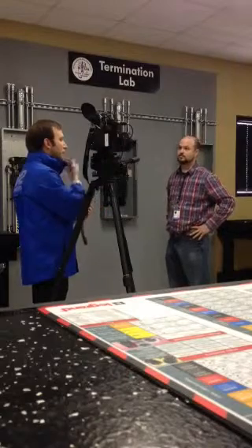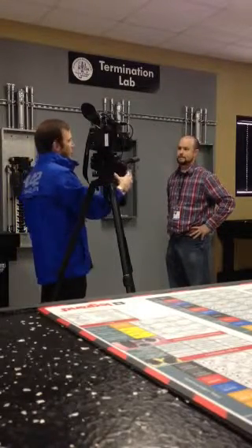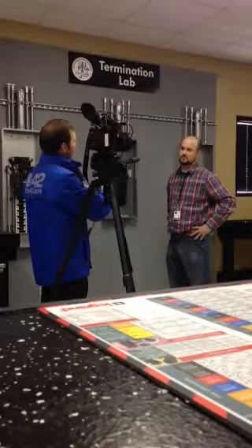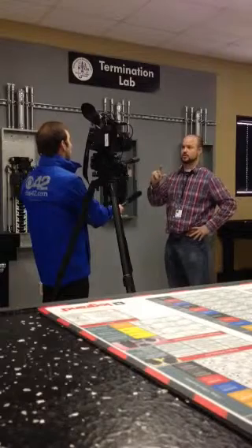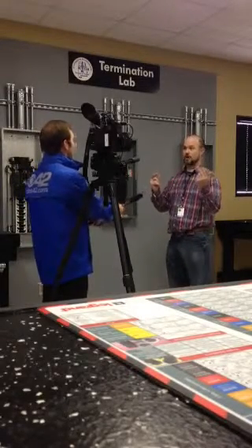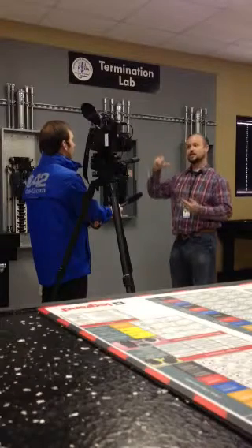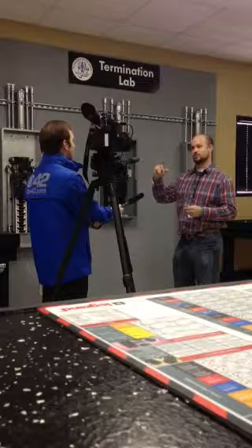And so I guess for people, what would be a copper thing you're connecting to? In other words, the device, the actual receptacle will be a copper receptacle. Coming off of whatever, the plug. And the wiring, aluminum wiring. So once you put aluminum wire under a copper receptacle, that receptacle has got to be rated for copper and aluminum.